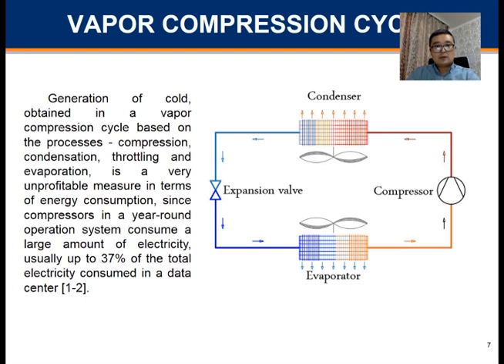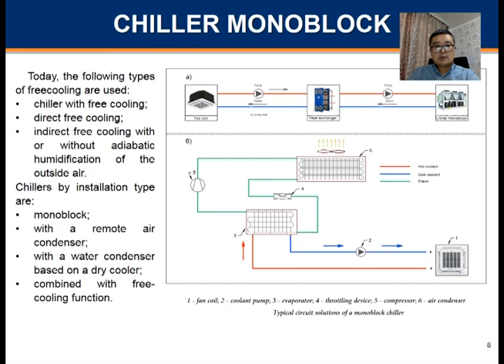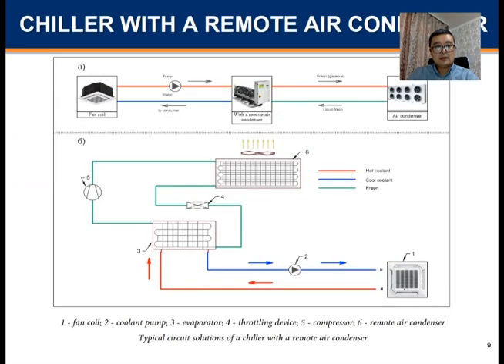Today, the following types of free cooling are used: chiller with free cooling, direct free cooling, and indirect free cooling with or without adiabatic humidification of the outside air. Chillers by installation type are monoblock, with a remote air condenser, or with a water condenser based on a dry cooler, combined with a free cooling function.